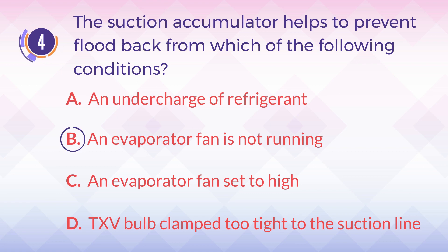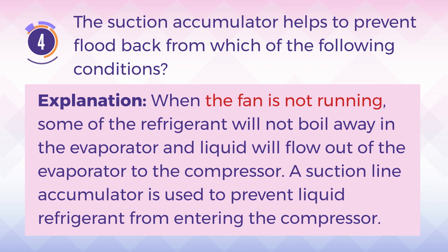The answer is B, an evaporator fan is not running. When the fan is not running, some of the refrigerant will not boil away in the evaporator and liquid will flow out of the evaporator to the compressor. A suction line accumulator is used to prevent liquid refrigerant from entering the compressor.